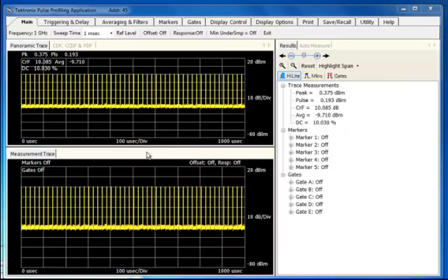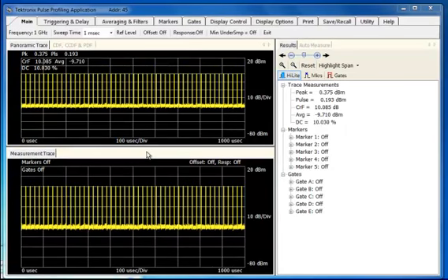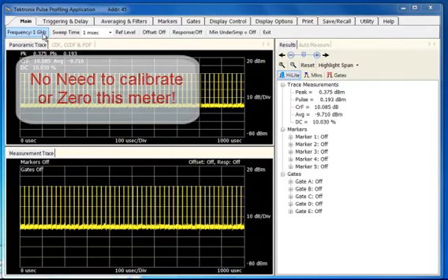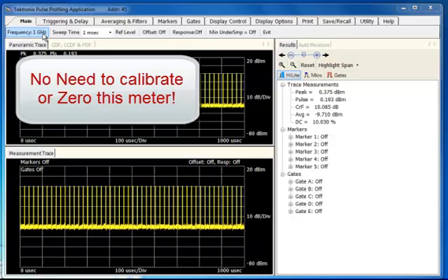Hello, we're looking at the pulse profiling abilities of the new USB pulse power meter sensors from Tektronix, the PSM5000 series power meter. This is the user interface that resides on the PC. Right off the bat, you can see that we can set the frequency, which sets the calibration table so that we get accurate measurements of this signal.